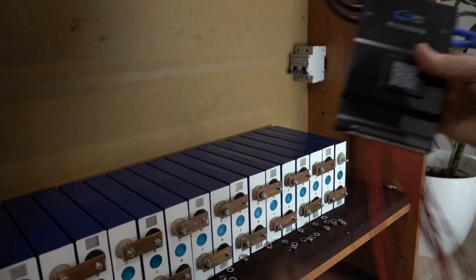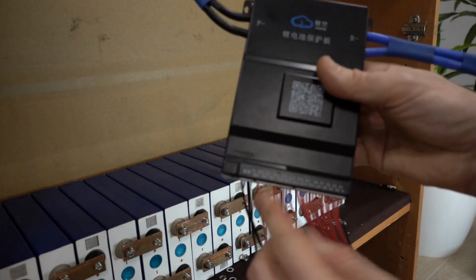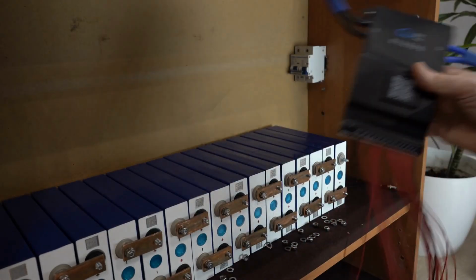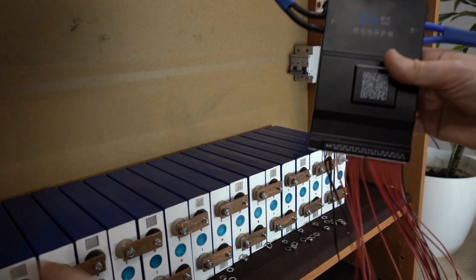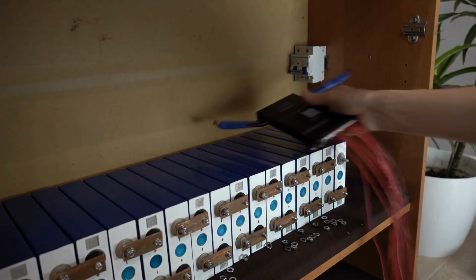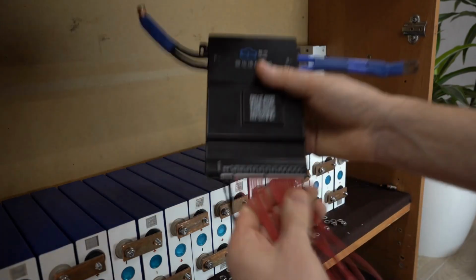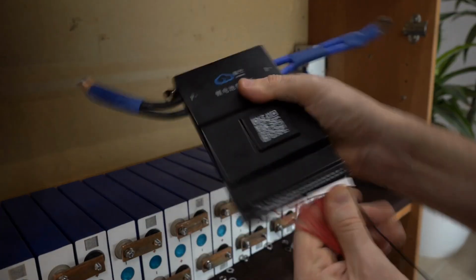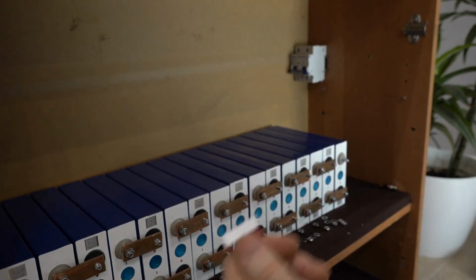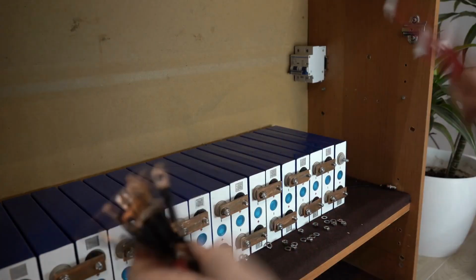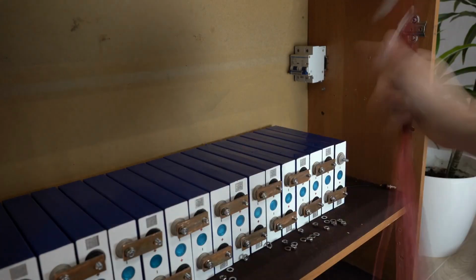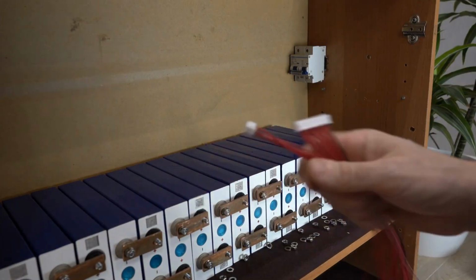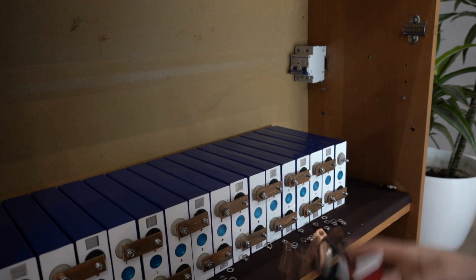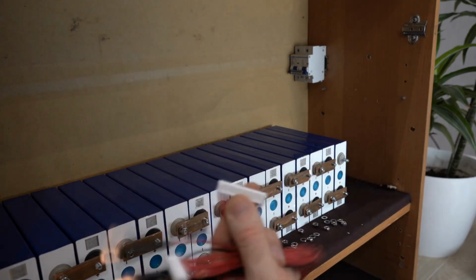It's recommended to first disconnect these connectors before connecting, then connect the wires in order, check them, and only then insert the connector. If you mix up a wire, you can burn out the BMS. So we first connect everything, and only then insert the connector into the BMS.